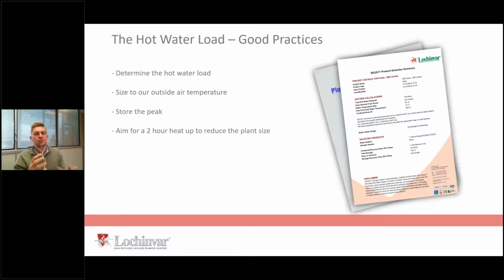Okay, so the industry spent a long time. Basically, what we used to do, I mean, we've probably all seen summer boilers and thought, oh, what a weird thing. Why would you have a summer boiler? Well, basically, we spent a long time putting in big calorifiers with little coils in, having long heat up times, and in the summer we'd run a summer boiler and turn off the main heating plant. And then we went towards a situation where we installed gas-fired water heaters with 300 litre storage vessels and 120 kilowatt burners, and we did everything semi-instantaneously, and we had that small volume there for peaks and troughs, right? Because gas is such a responsive technology.